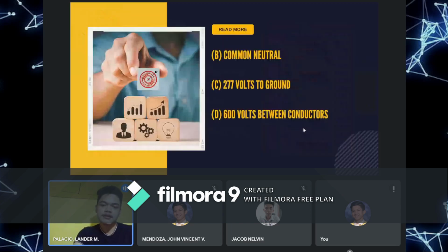So, it states here, sa common neutral, okay, ito na yun. What is common neutral? Or ano ba yung nakapaloob dyan sa common neutral na yan? So yung common neutral, sinasabi lang dito that the ampacity of the neutral conductor shall not be less than the maximum net computed load current between the neutral and all ungrounded conductors connected to any one phase of the circuit. So Article 225 covers yung ganitong rule for installation of outside branch circuits like what I have mentioned earlier. And for the branch circuits and feeders.